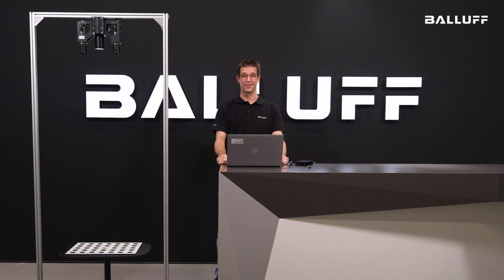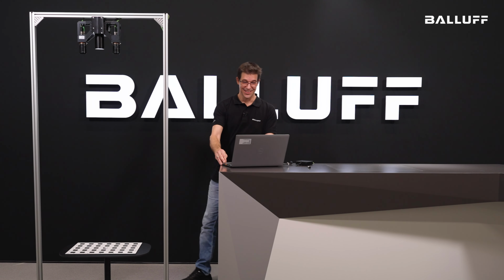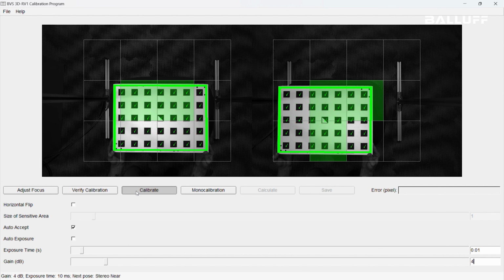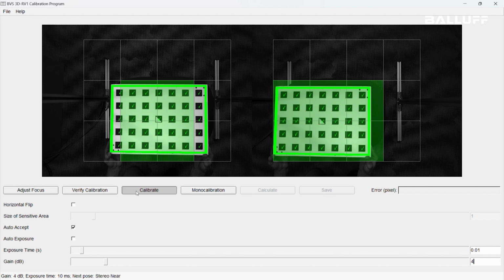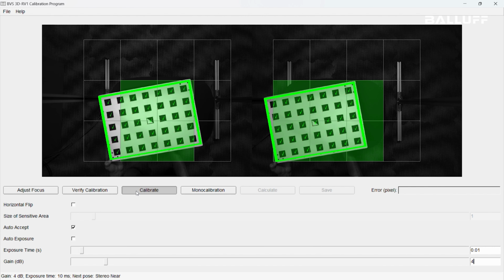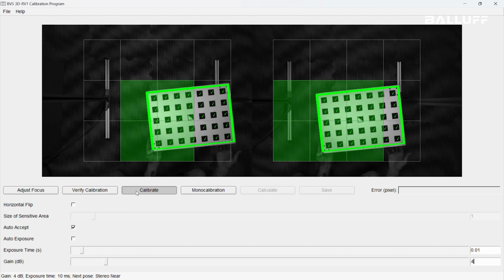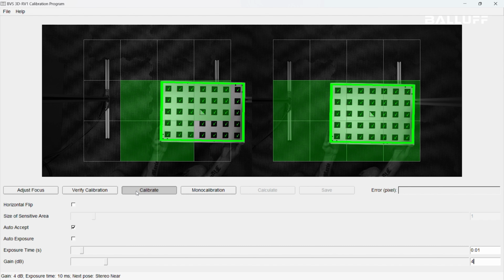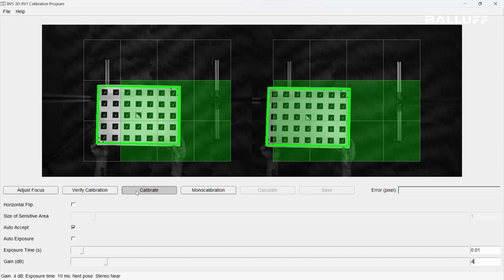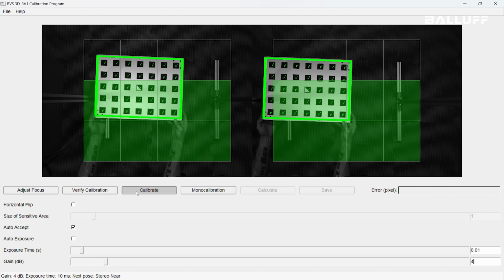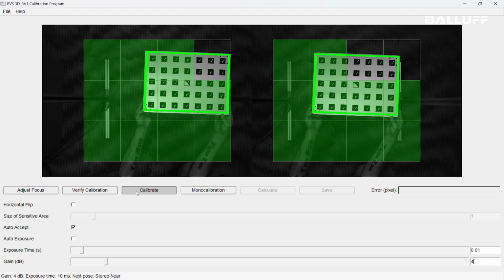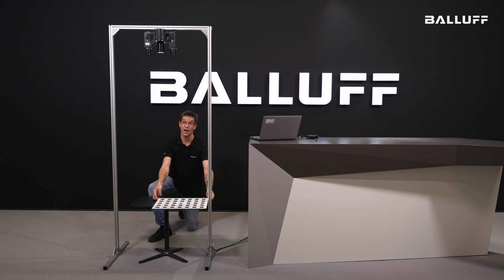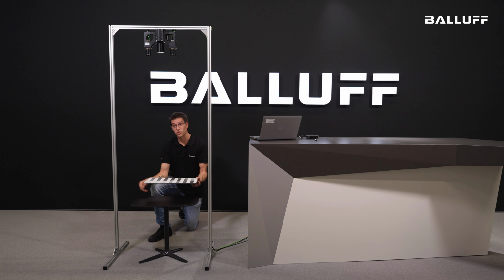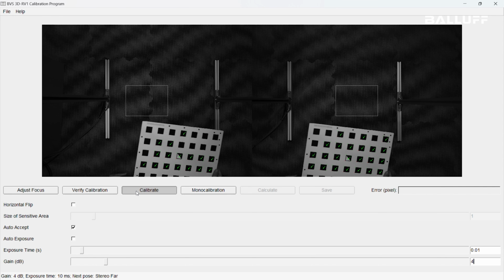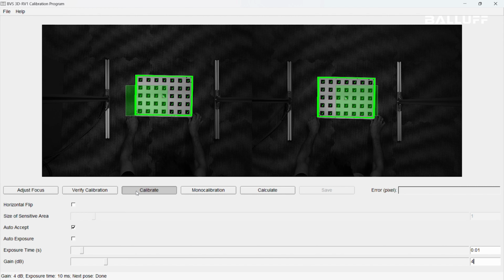So let's start with the second step, refreshing the stereo calibration. Therefore, we place the plate as close as possible to the system and move the plate into different positions as well to cover all of the visualized cells until they get marked in green. If all of the cells are covered, the final step to finish the stereo calibration would be to move the plate to a farther distance, roughly 400 or 500 millimeters should be enough, to cover the last cell in the center of the image.